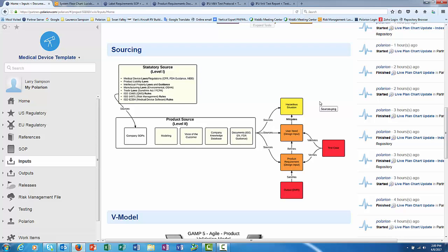And so we need a level of abstraction to avoid having the design impacted by two levels of requirements. I don't want to have to break down 14971 and break down the company SOP and trace those requirements into the design control. So with this pre-processing abstraction, we break them into different types of work items so that we don't impact the product directly by all this chaff that's outlying our SOP process.